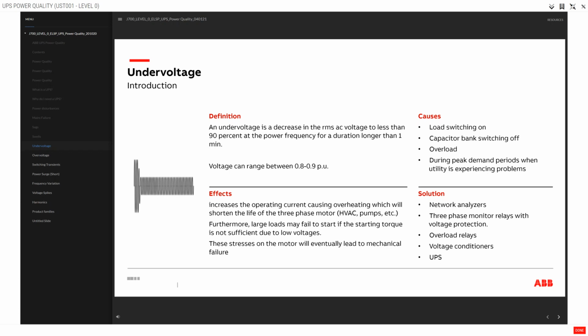Increases the operating current causing overheating, which will shorten the life of the three-phase motor, HVAC, pumps, etc. Furthermore, large loads may fail to start if the starting torque is not sufficient due to low voltages. These stresses on the motor will eventually lead to mechanical failure. Solution: network analyzers. Three-phase monitor relays with voltage protection. Overload relays. Voltage conditioners. UPS.